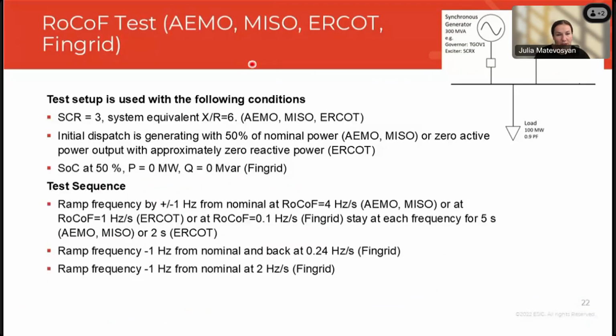RoCoF test, again defined by AEMO, MISO, ERCOT, and Fingrid, has a relatively similar test setup, with a bit different dispatch levels. The frequency is ramped by plus minus 1 Hertz from nominal, at 4 Hertz per second in AEMO and MISO tests, ERCOT test at 1 Hertz per second, Fingrid tests at a relatively small 0.1 Hertz per second, and then stay at each frequency for 5 seconds before repeating the test, and 2 seconds defined by ERCOT. And then 2 more tests defined by Fingrid at different levels of RoCoF.